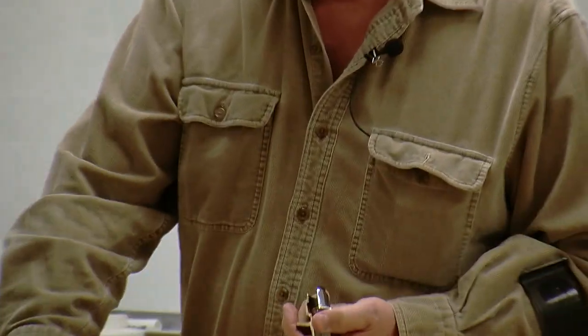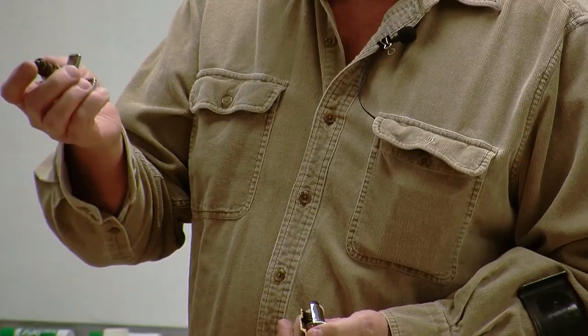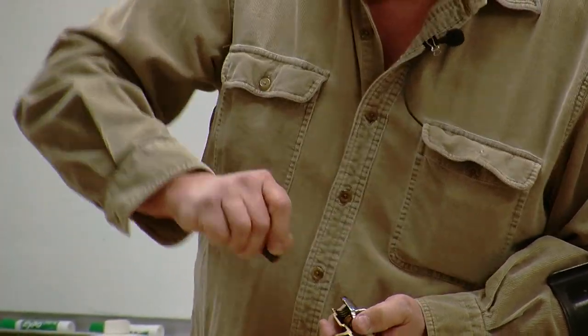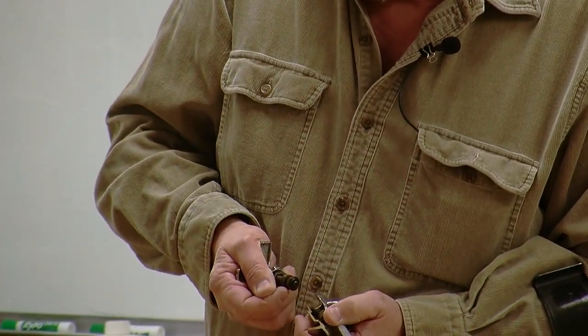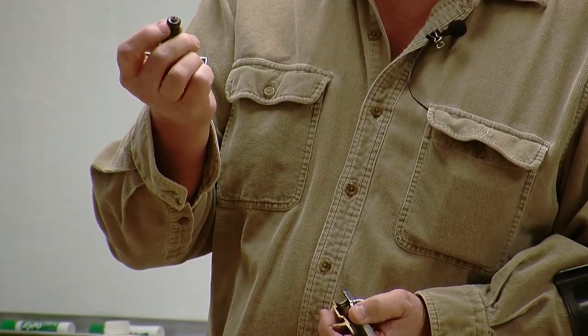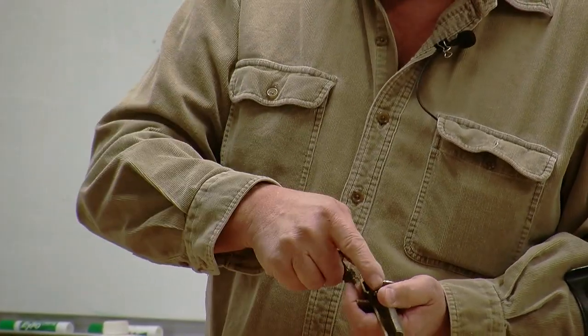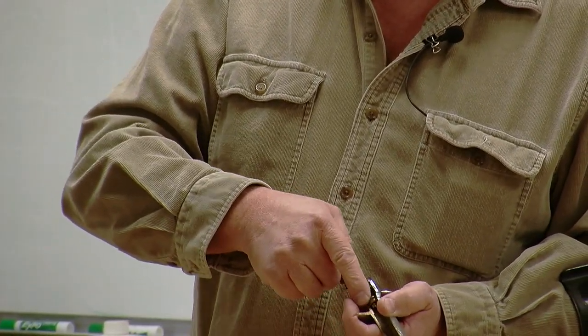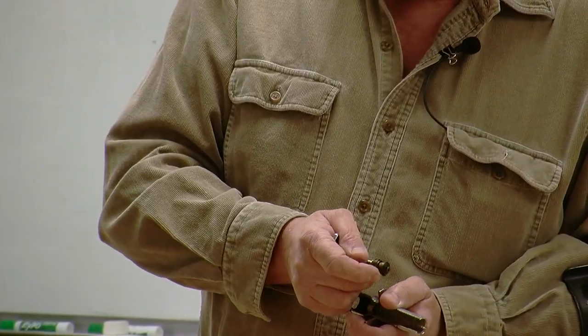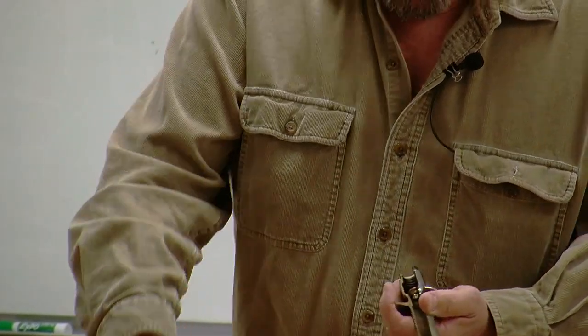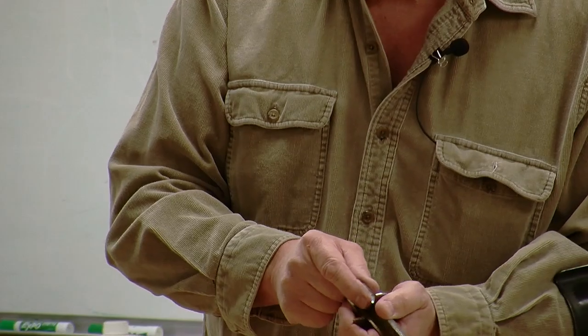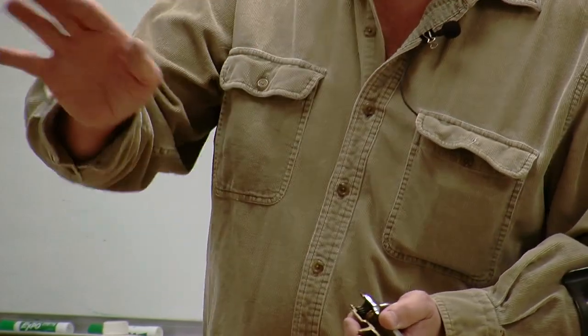Okay, now, once you have this out, you'll look down in here, and when I pass this around, you'll see it. There's a seat. What this seat does is it receives this rubber. But when the rubber wears out, sometimes you keep cranking it more to try and get it to stop leaking. What you do is you actually run the brass into the seat and wear the seat out. Once you wear the seat out, no matter what you do, you won't be able to get a good seal. So what we do is we replace the seat. These are on stock, right on the shelf.